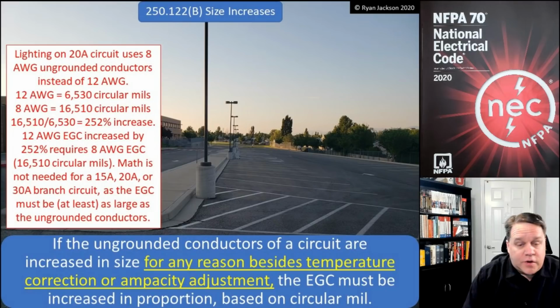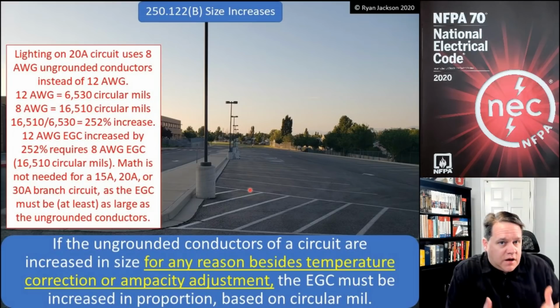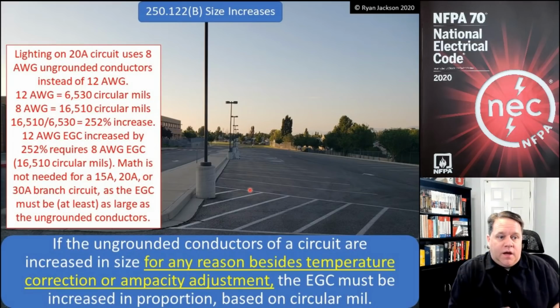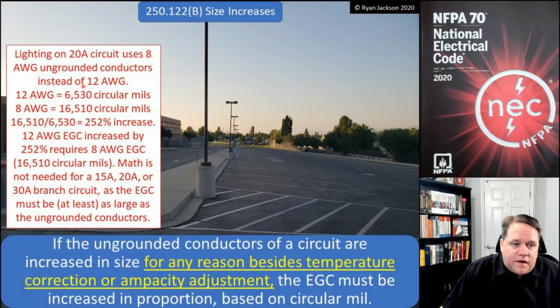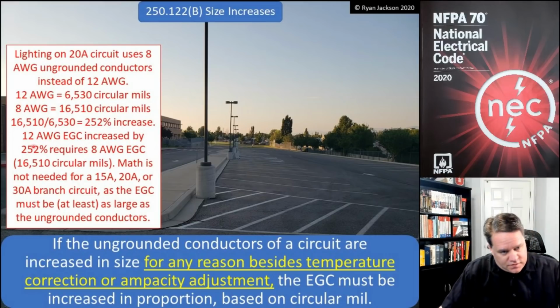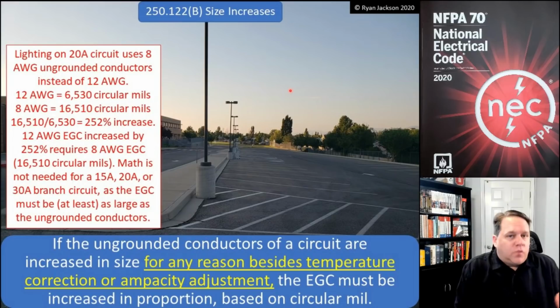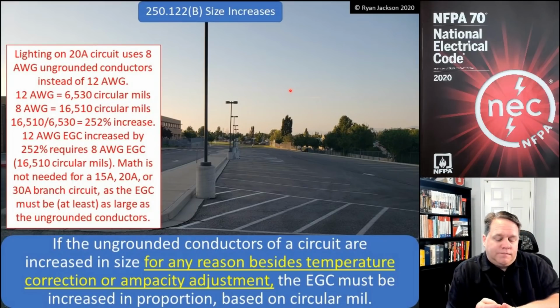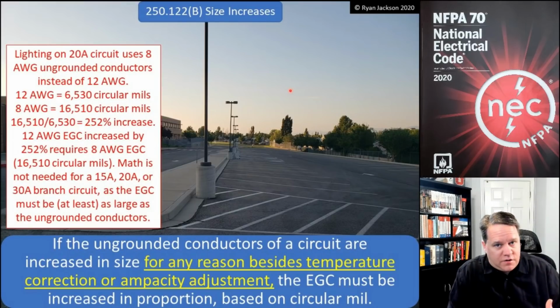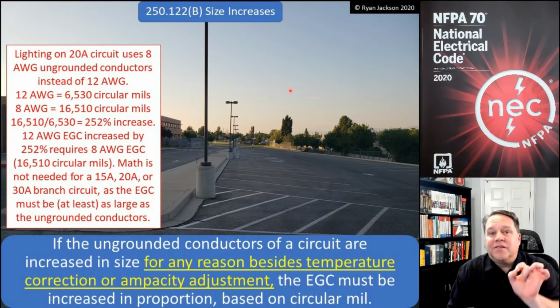So the 12 gauge equipment grounding conductor needs to be increased by a factor of what? 252%. Okay, so I know that I start at a 12 gauge equipment ground for a 20 amp circuit, and I need to increase it by 252%. Okay, well, we know that 12 gauge is 6,530 circular mils. If we increase it by 252%, it's going to yield what? 16,510, which is an 8 gauge. And that's why I said earlier that for a 15, 20, or 30 amp branch circuit, the size of the equipment grounding conductor has to be the same size as the ungrounded conductor. Because if you increase one, you have to increase the other in proportion.